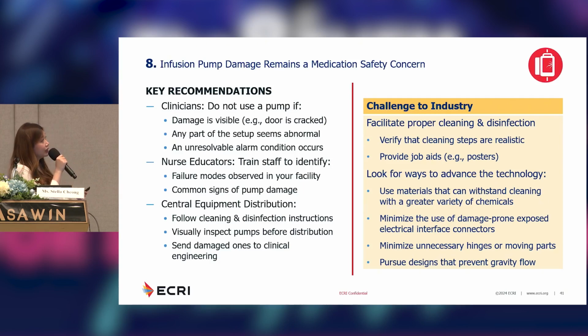Right. And this is also a challenge to the industry, meaning our manufacturers of infusion pumps. We need to facilitate better processes in the use and maintenance of infusion pumps. One way that we can do this is to facilitate proper cleaning and disinfection, because a lot of the time, pump damage can result from using improper cleaning or disinfection reagents or liquids on the pump, which then compromises the integrity of the pump modules, leading to further damage. So what the industry can do is facilitate this cleaning process by providing realistic and practical cleaning steps to our users, and also providing job aids, for example, posters or infographics, to make the process easier to understand and easier to conduct.